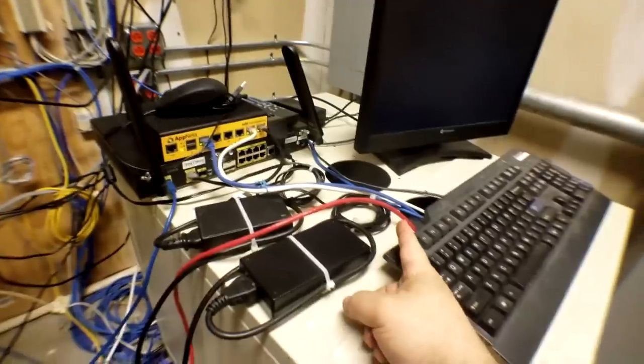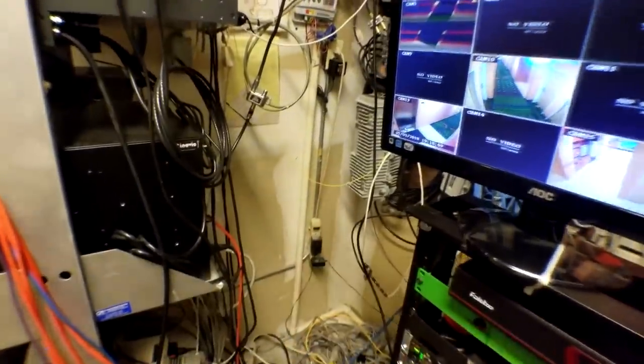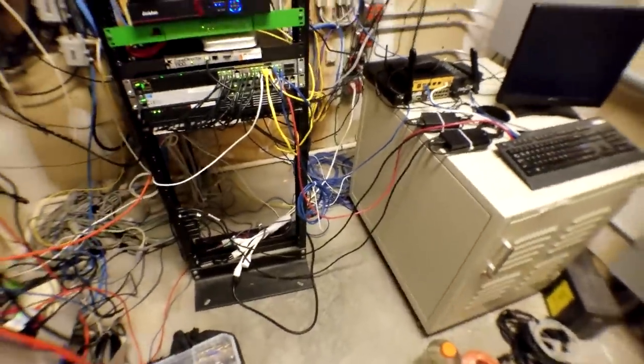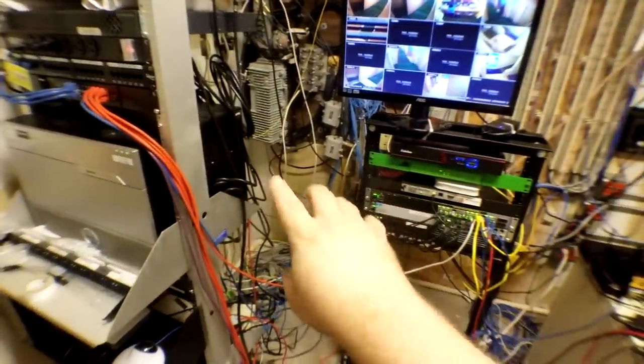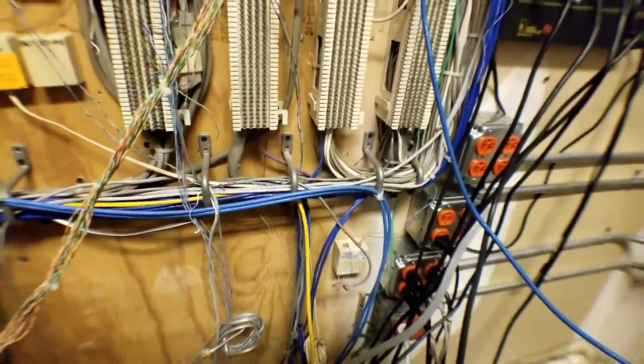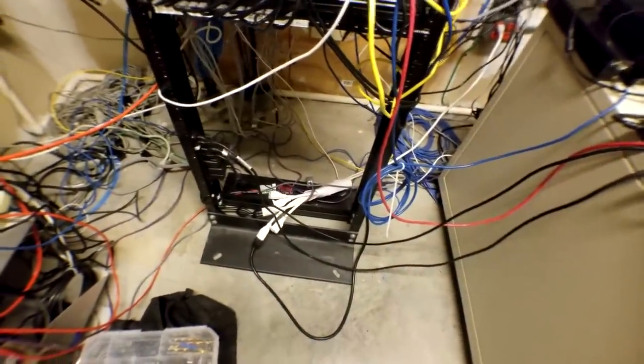There were also holes that hadn't been opened, so cables ran out around the front door to get where they needed to go. There's still a lot to be done, but my goal was to clean up enough of the floor to safely access the back wall. Now I'm going to deal with cables being draped between equipment. You need to keep your cables out of harm's way by putting up J-hangers so the cables run along the wall — that's how telco equipment is run. Next I'll also be replacing a lot of these cheap outlet strips with real PDUs.